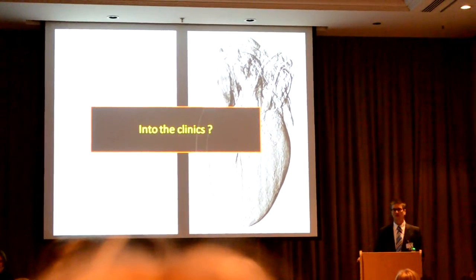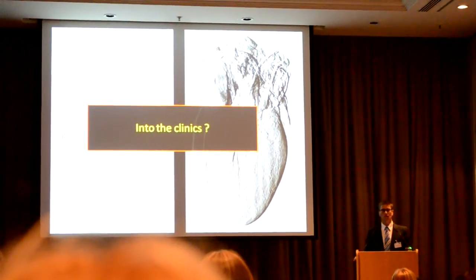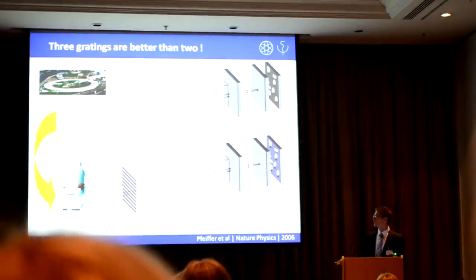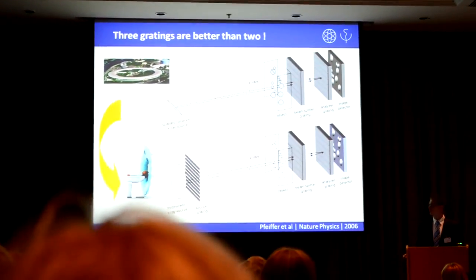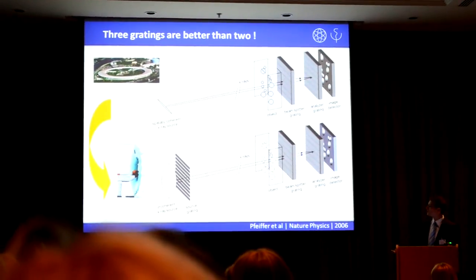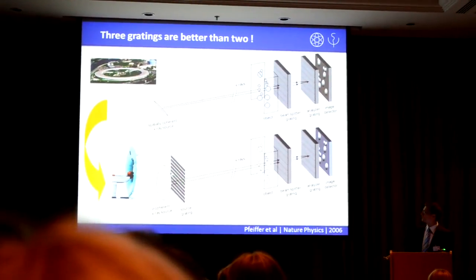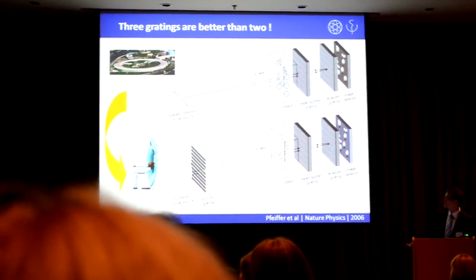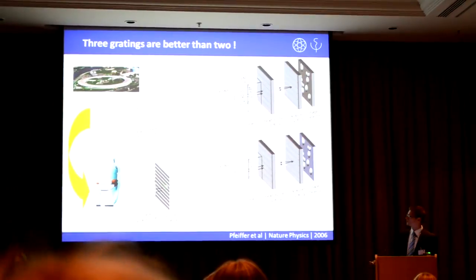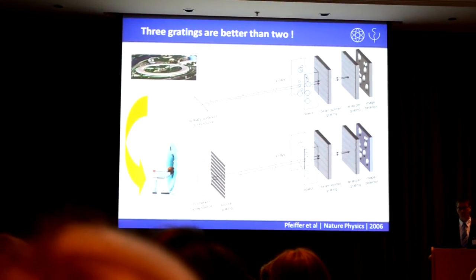With these nice images, we asked ourselves at some point: is there a potential to drive this into clinics? Can we go from large-scale synchrotron sources with very brilliant X-ray beams to clinically relevant X-ray tubes? The trick we were using at that time is also a trick we learned from atom interferometry. It essentially allows us, by placing yet another grating in front of an incoherent X-ray source, to simulate partially coherent X-ray beams or line sources which have a very narrow dimension in this direction.